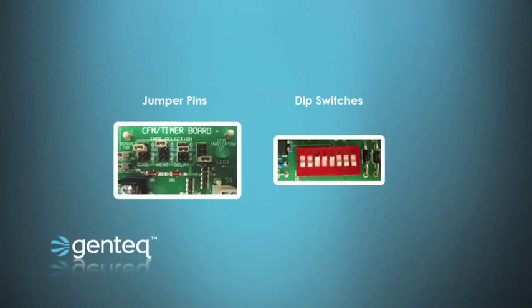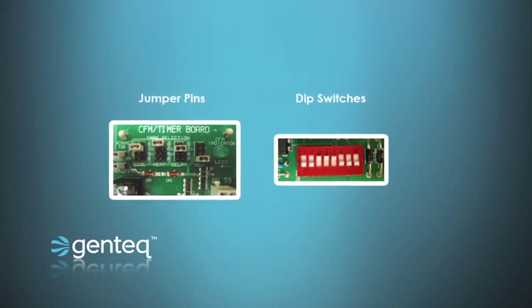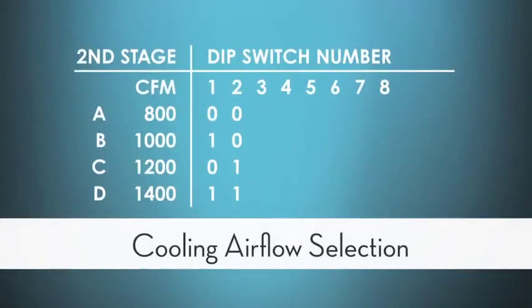The HVAC manufacturer will put on their circuit boards in the furnace, air handler, or package system — dip switches, jumper pins, dials, or even model plugs — that will allow you to select the proper airflow for heating, cooling, constant fan, dual fuel systems, electric strips, every airflow point that needs to be set up in that system, and your enhanced comfort options. The charts used to set those switches look like what you see here — and this is just an example, as every manufacturer does their charts a little differently.